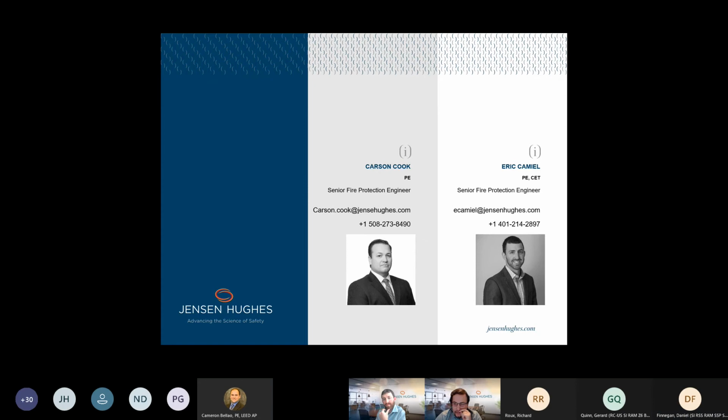I think you'd still want to see a closer on it, especially because somebody could be working on that and a fire could occur and they may not think, okay, I have to close this before I leave. So I think you'd still want to see the closer on that. I was recently out at a site where there was a small BDA closet that had a 2-hour door on it, and the building inspector brought up that the door should have a closer on it. So I would say it's good design practice, to err on the side of caution, to include closers on those doors for that exact reason.